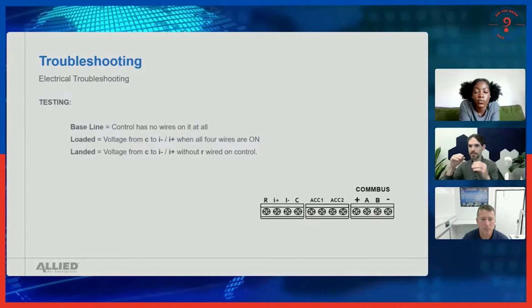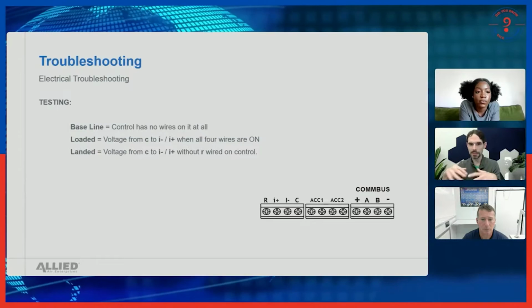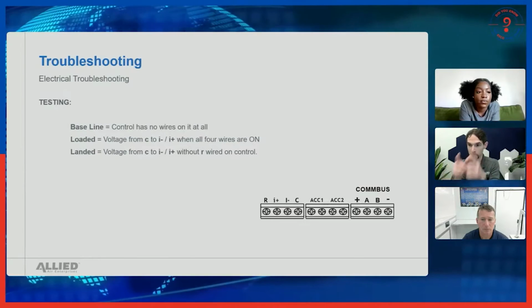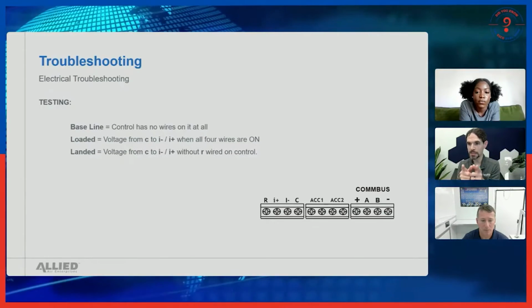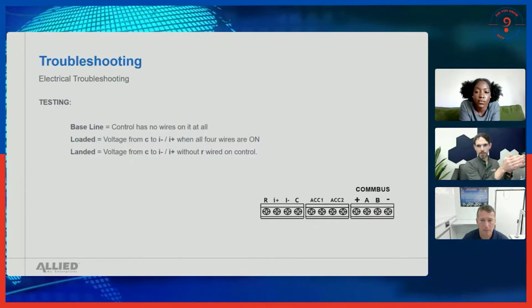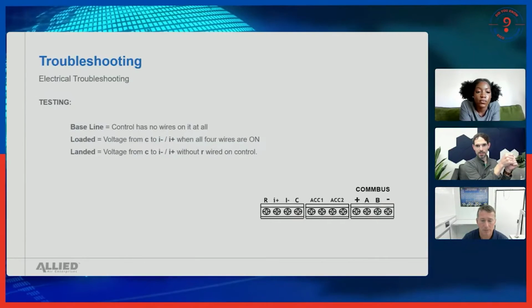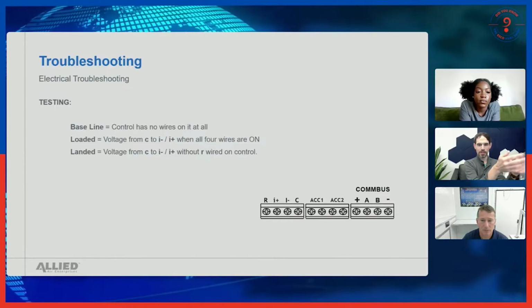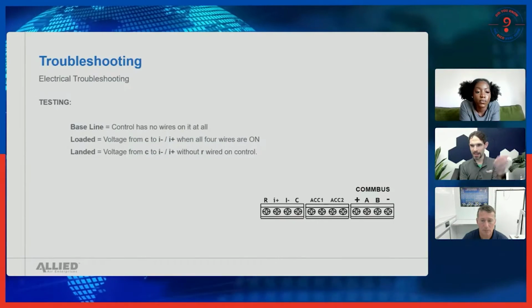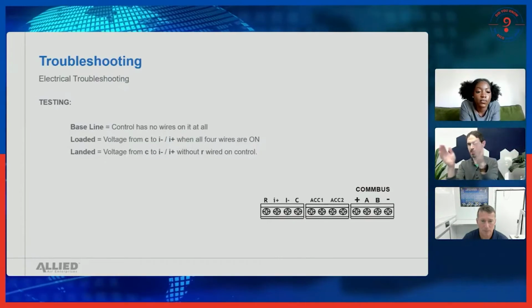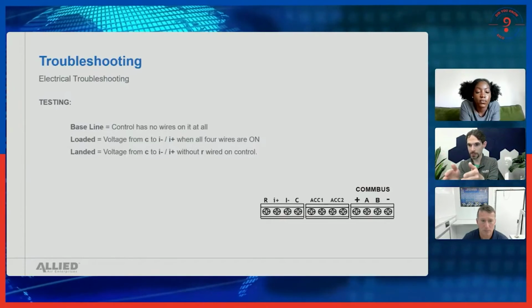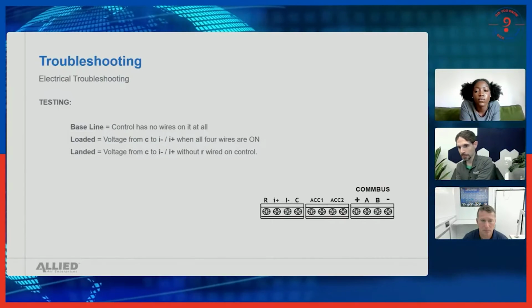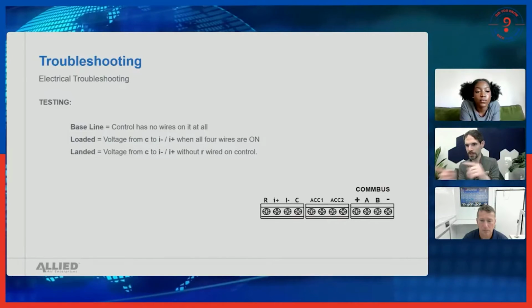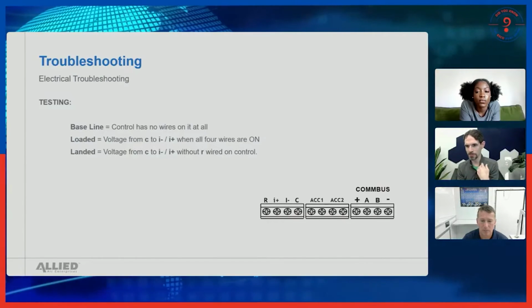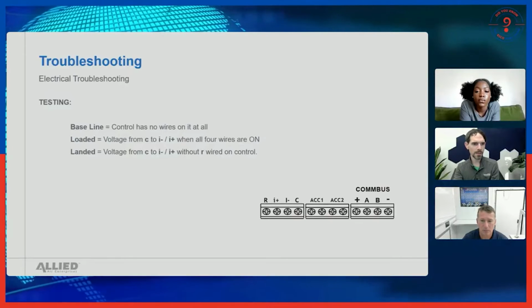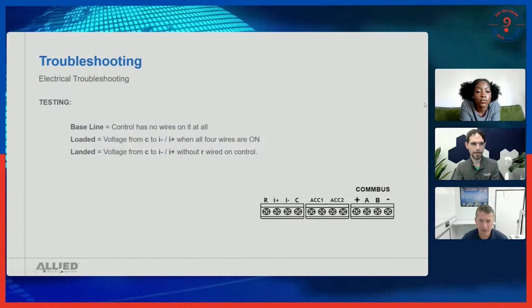Lastly, also look at it straight from ground to the wire without any power, and where that reads. That can help diagnose if it's a component that might be the problem. If I'm looking all the way on the indoor side and checking here and not getting anything, well, I should be, because I'm at the indoor. So do I have proper power coming in? Am I looking at, in our case, the hub that's in the middle? Or am I looking all the way down at the display? Is there something not reading in the to or from direction? I can check that by reading DC voltages.